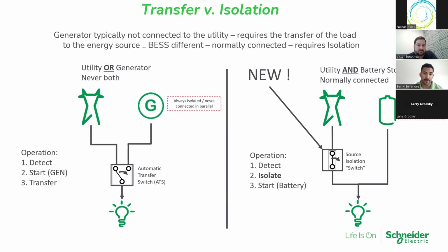Once that voltage and frequency drop out, it will isolate, so it'll open that breaker and send the contact signal or start signal to the battery energy storage system, the power control systems, the inverter systems, to change state from grid-tied to grid-forming mode, where at that point the energy storage system is now safely segmented. You've segmented your essential loads, and you're providing backup power to those essential loads only, isolating the rest of your facility. So in the event that utility does return, you don't have to worry about a backfeed. You're safely isolated, and then the source isolation switch can detect that utility has returned and signal the battery inverters to shut down and operate again in grid-tied operation.